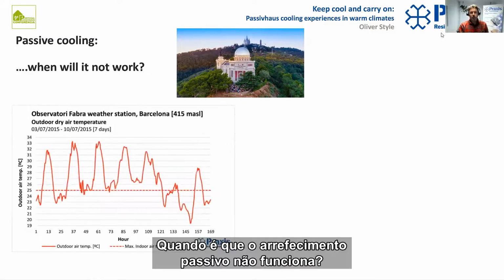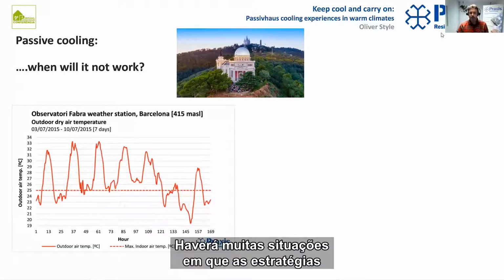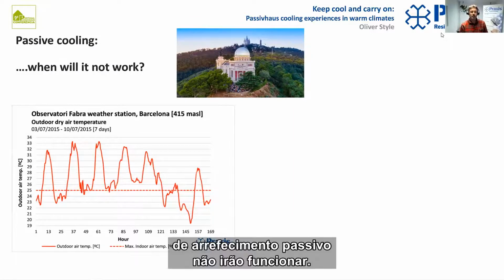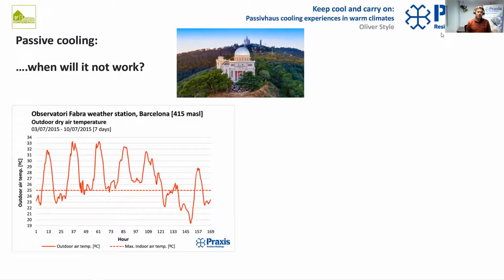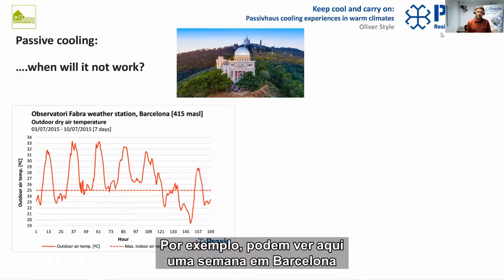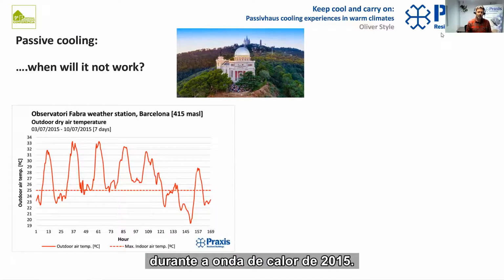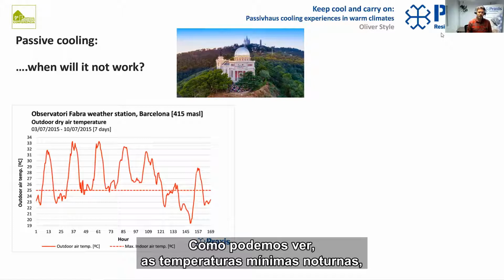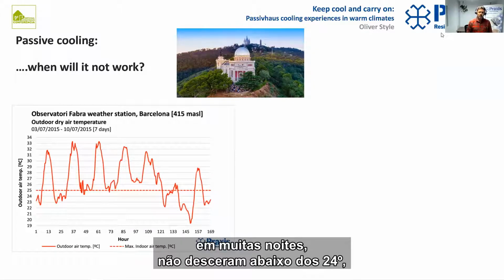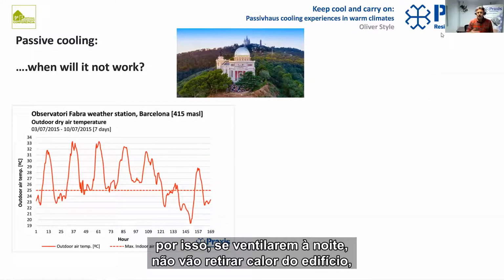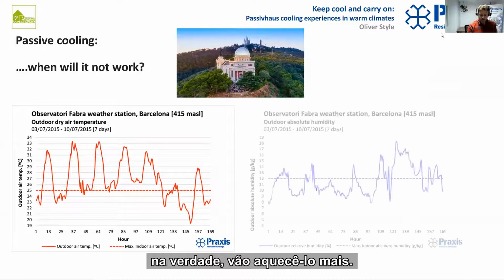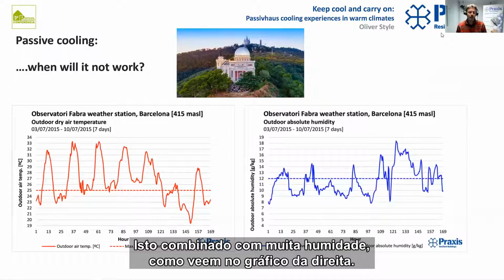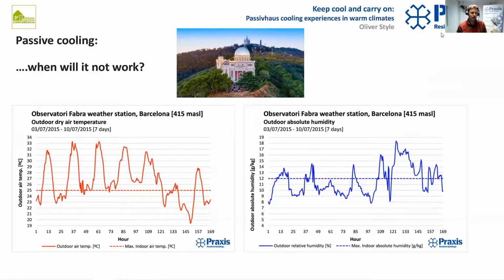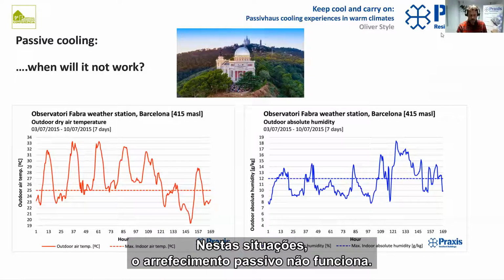So passive cooling, when will it not work? Well, there will be many situations in which the passive cooling strategies won't work. The ones I've just presented here. One example is what you can see here of a week in Barcelona during the heat wave of 2015. So what we can see is that minimum night temperatures in many of the evenings didn't drop below 24 degrees. So if you ventilate in the night, you're not going to take any heat out of the building. In fact, you're just going to heat it up more, combined with large amounts of humidity in outdoor air, which you can see in the graph on the right. So passive cooling in these kind of situations isn't going to work.